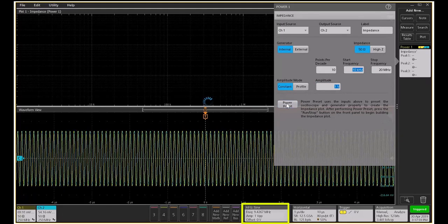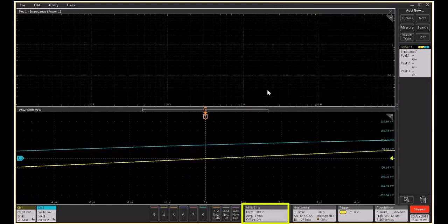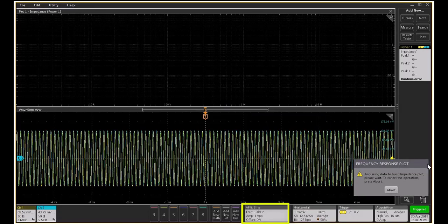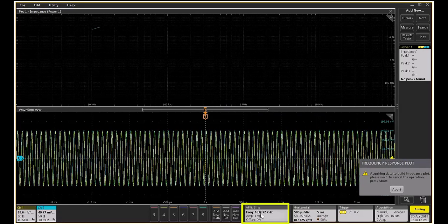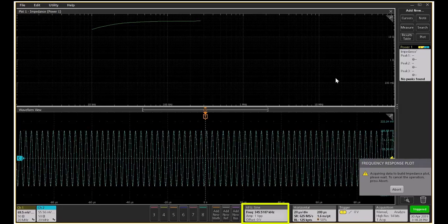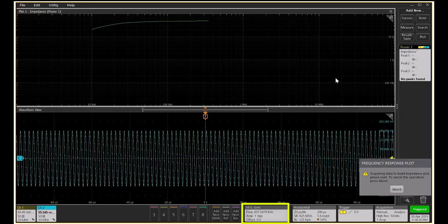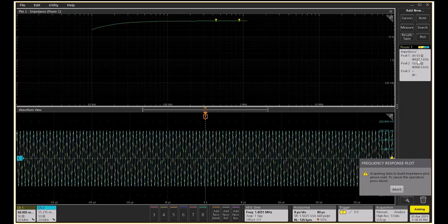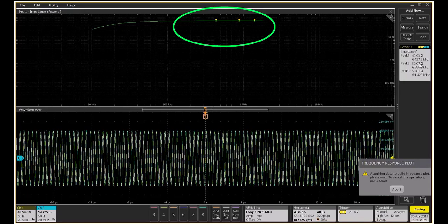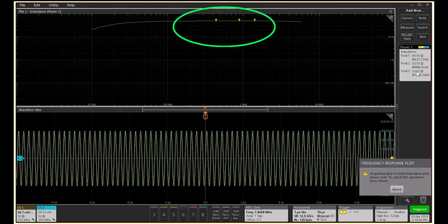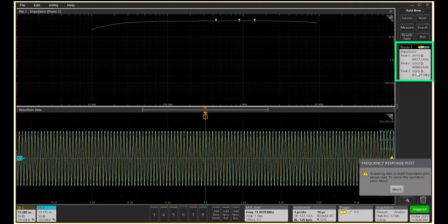And once we set the power preset, the software automatically invokes the AFG option. And now the software starts sweeping from start to stop frequency. The signal from the AFG output through the power divider, whether passive or active, is fed into channel 1 for reference, and channel 2 is coming from the reflected signals out of the DUT. The output of the DUT is connected through the J2113 or J2102 Picotest transformers.